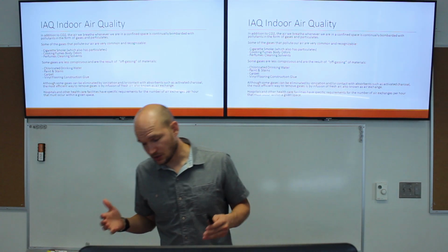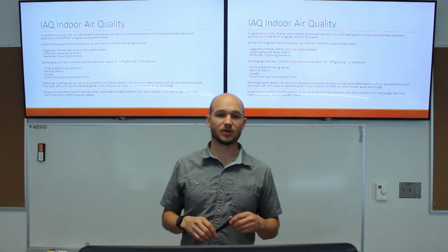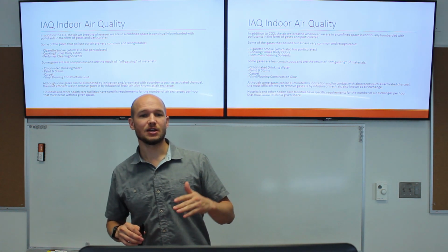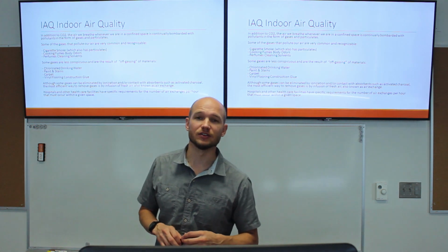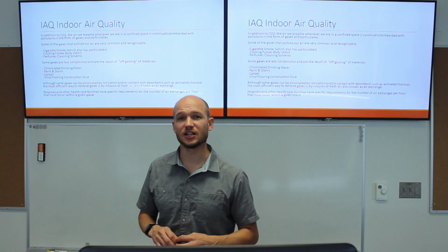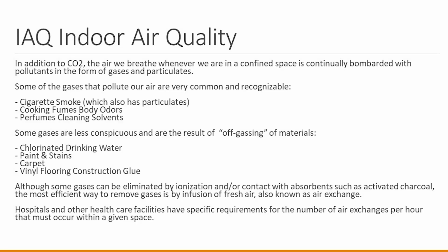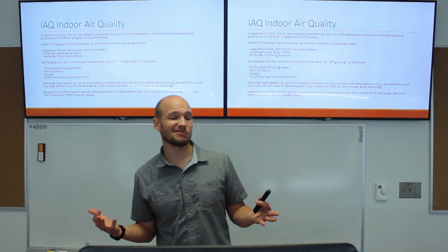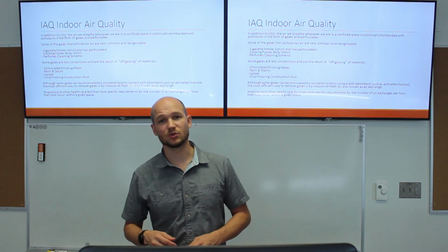So here we dig into the indoor air quality a little bit deeper. CO2 is an important number, but you also have gases that can pollute the air. And so why do we need to bring in fresh air? Why is it a requirement by ASHRAE and built into the sequence of operations? Because there's other things, right? There's potentially cigarette smoke, there's cooking fumes, there's body odor, there's perfume, there's cleaning solutions, and then there's gases that you may not even think about, sometimes referred to as off-gassing.